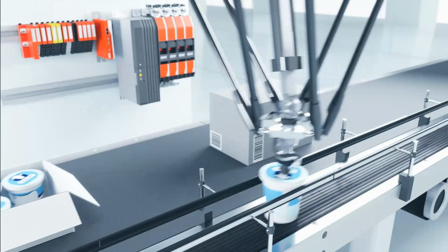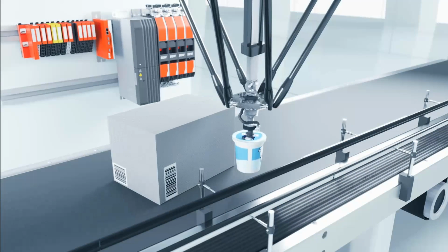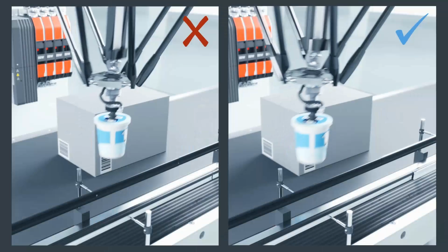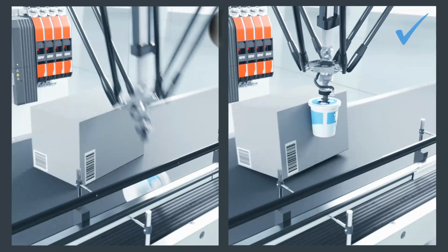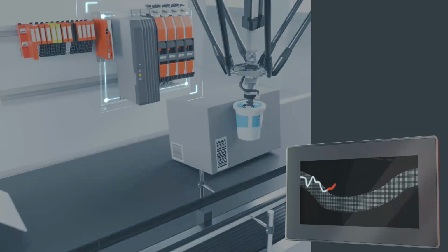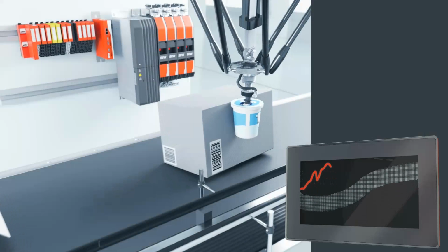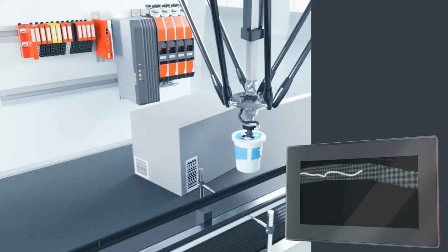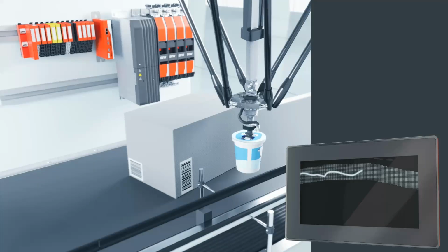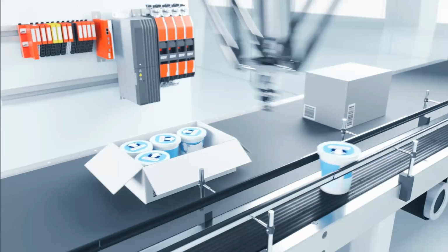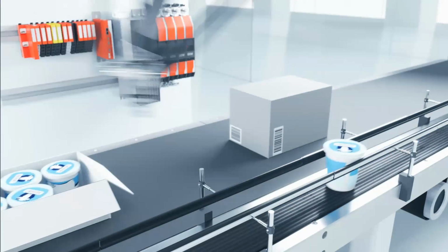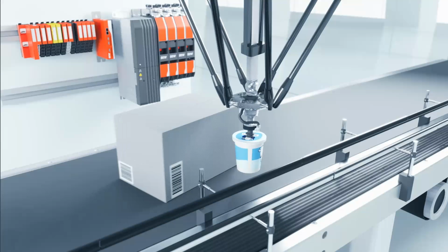With collision detection activated, however, in the event of a collision, the robot will be stopped immediately with path fidelity. Due to the unexpected collision, user intervention is still required, but with a decisive difference: the risk of damage or contamination is reduced by orders of magnitude.